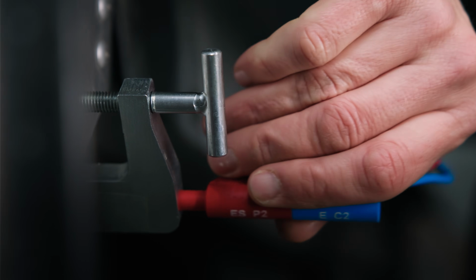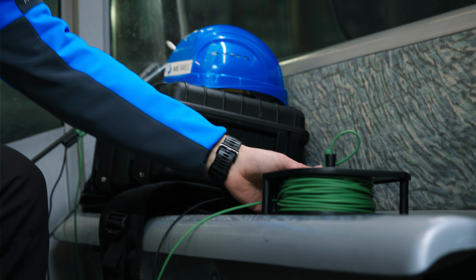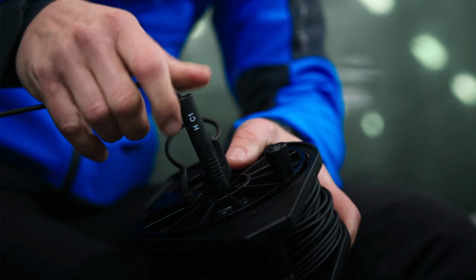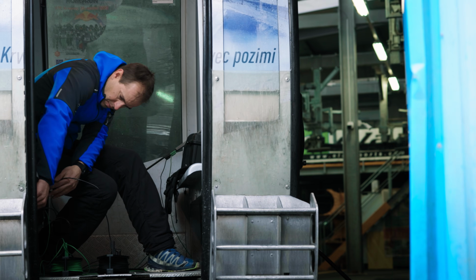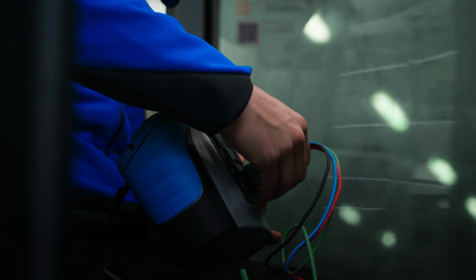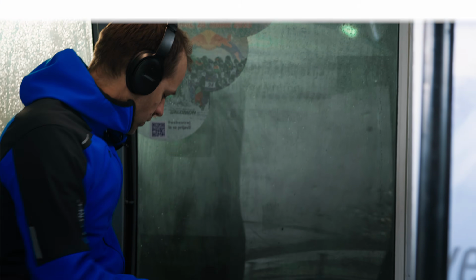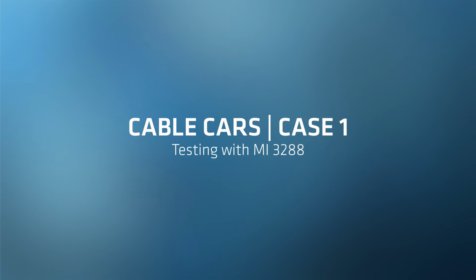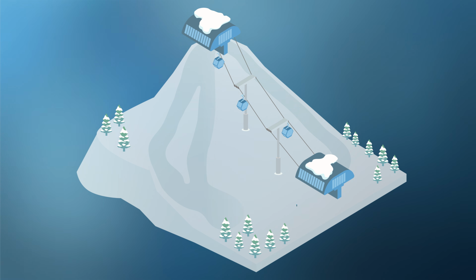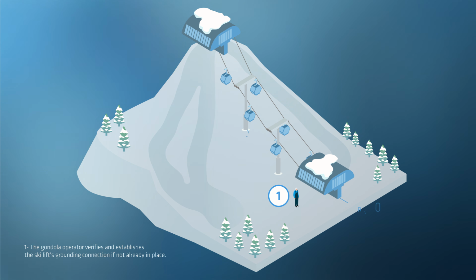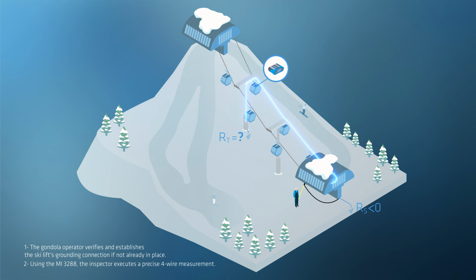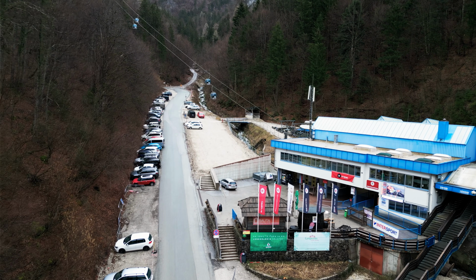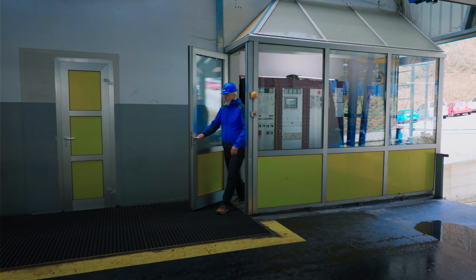We use a G-clamp to ensure solid contact with metal surfaces, even when they are covered with thick paint or rust. To achieve more accurate and reliable measurements, the 4-wire Kelvin method is applied. A communication headset is also essential, enabling clear coordination with the gondola operator throughout the testing process. The inspector moves along the gondola or chairlift system using the lightweight MI3288 tester to perform local potential equalization with a test probe, and with that, it creates a loop through the grounding. The inspector performs grounding resistance measurements for each tower. Working closely with the gondola operator, the system is stopped at each tower to allow testing.